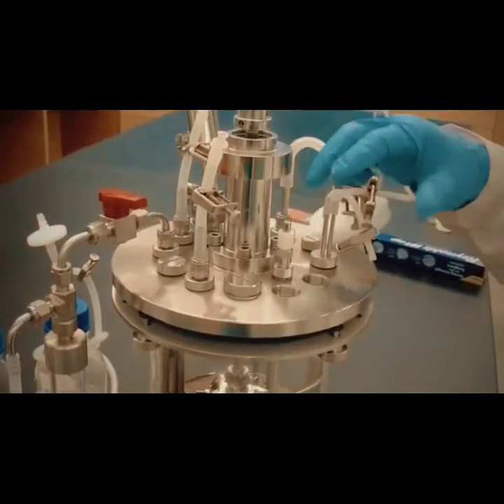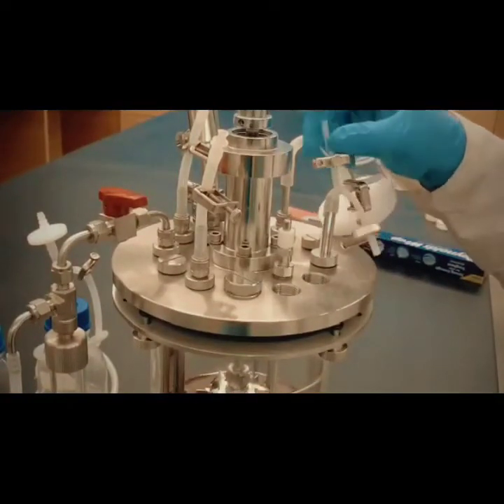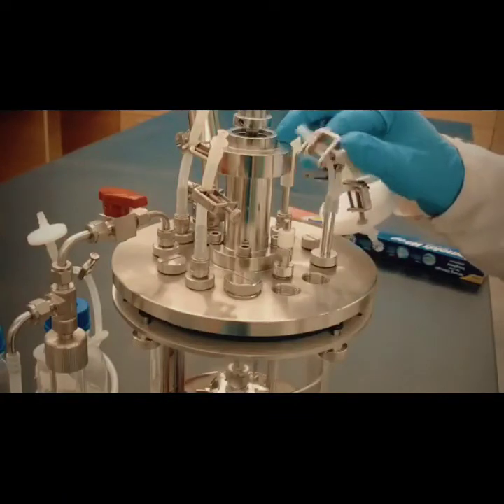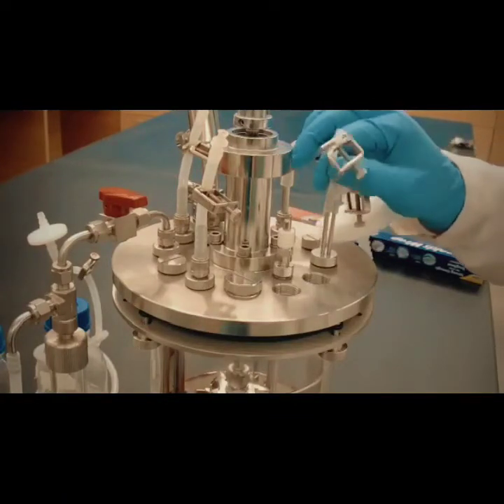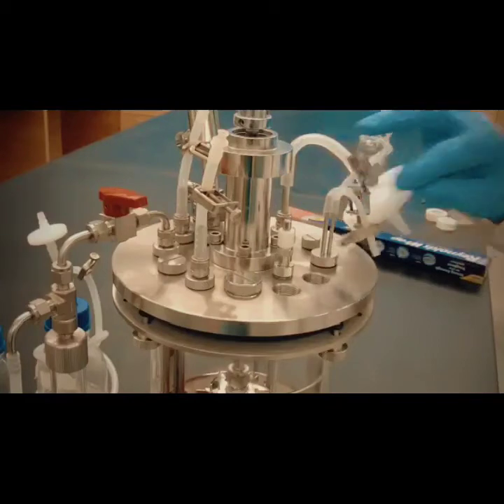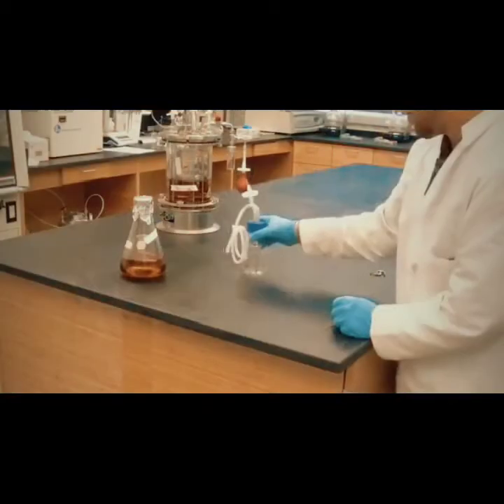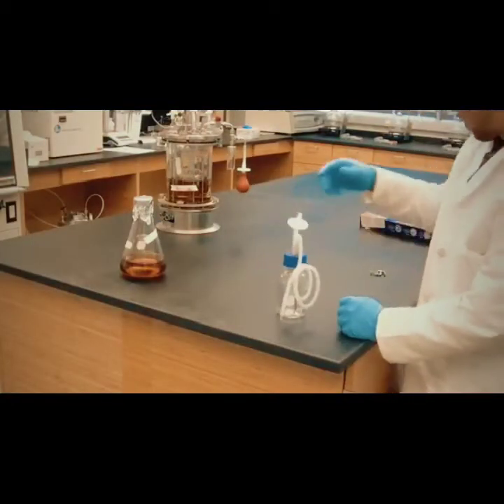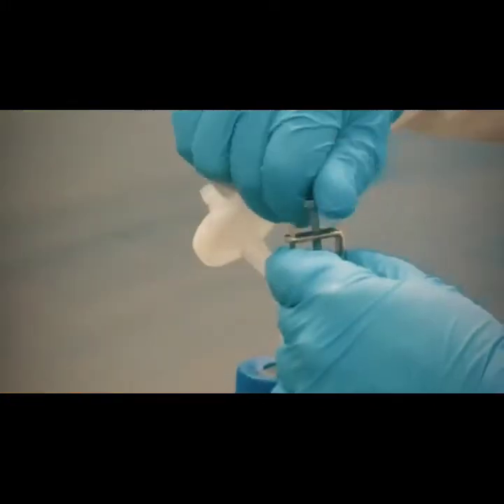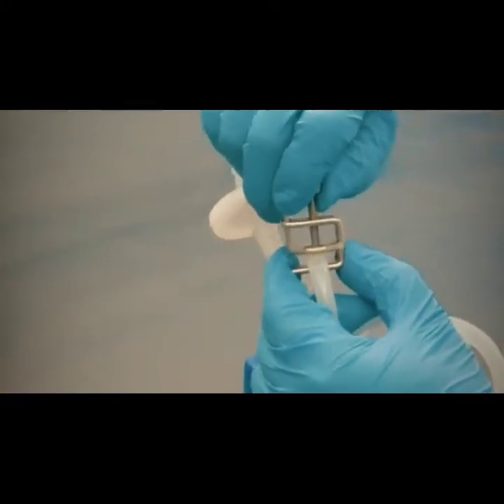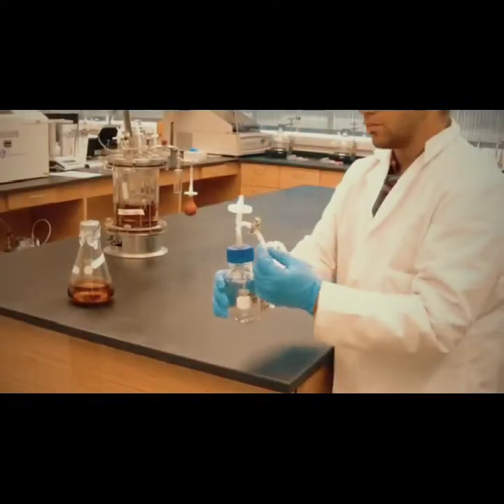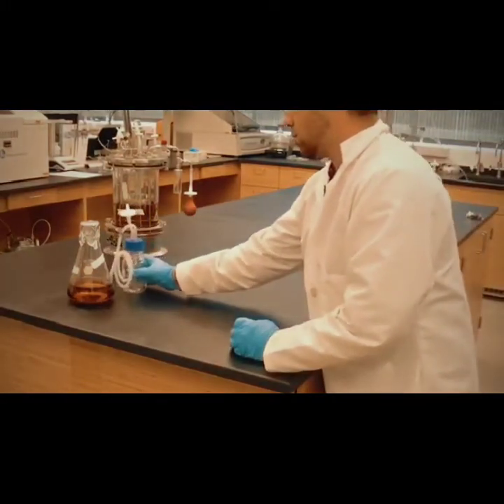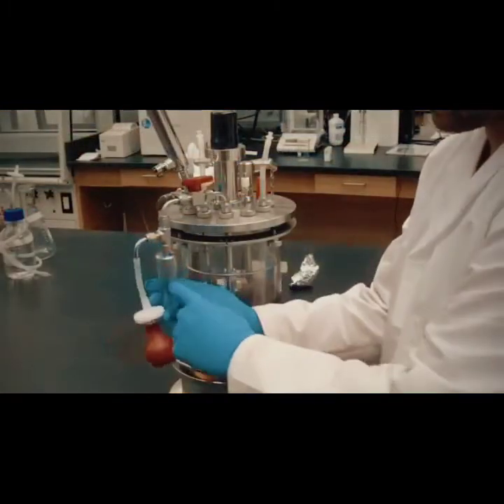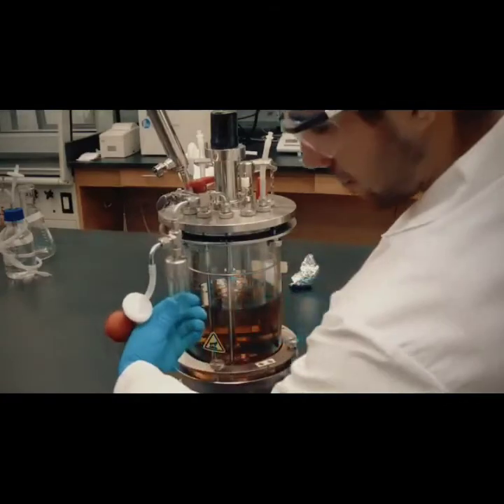Clamp off all tubes that have penetrations which go below the internal liquid level to prevent boiling over during autoclaving. Remove the resistance temperature detector from the thermowell. Make sure all solutions are covered with aluminum foil, marked with indicator tape, and labeled, and that the sugar addition bottle is clamped. Loosen the glass sample bottle on the sterile sampler about 1/2 turn.